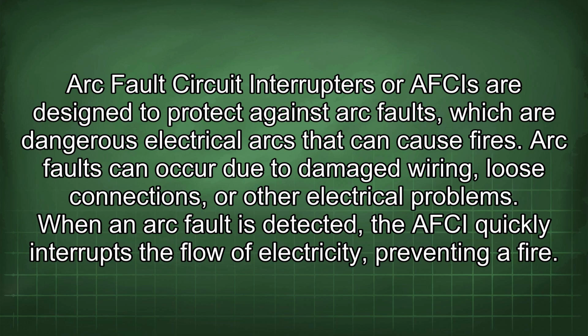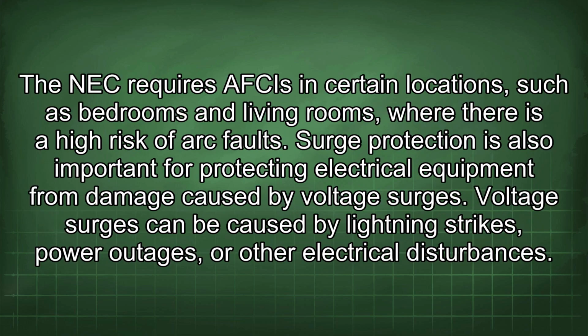Arc faults can occur due to damaged wiring, loose connections, or other electrical problems. When an arc fault is detected, the AFCI quickly interrupts the flow of electricity, preventing a fire. The NEC requires AFCIs in certain locations, such as bedrooms and living rooms, where there is a high risk of arc faults. Surge protection is also important for protecting electrical equipment from damage caused by voltage surges.